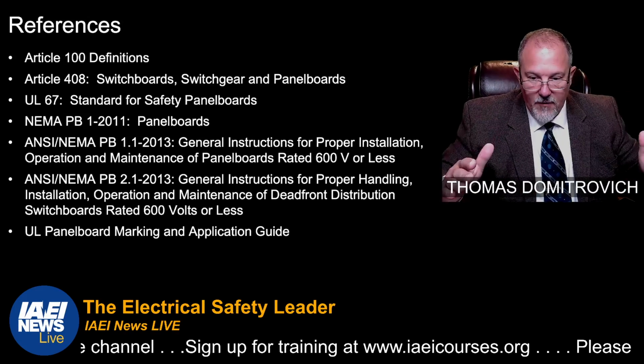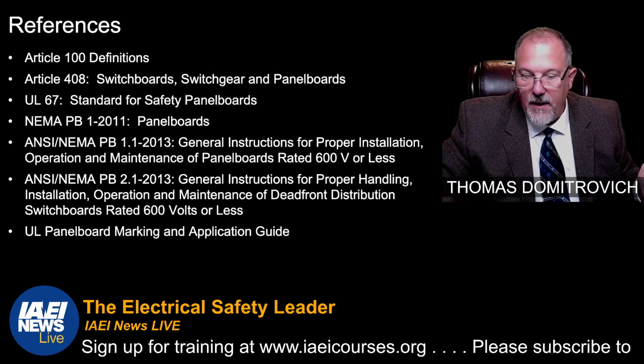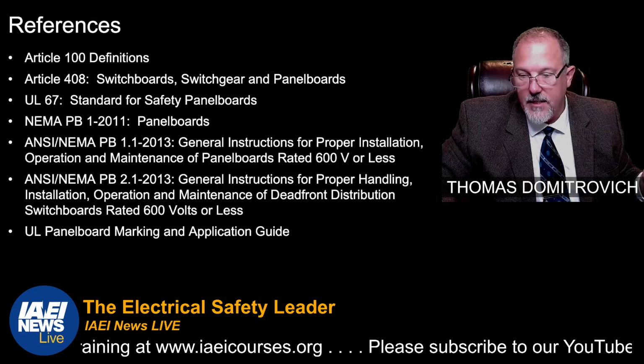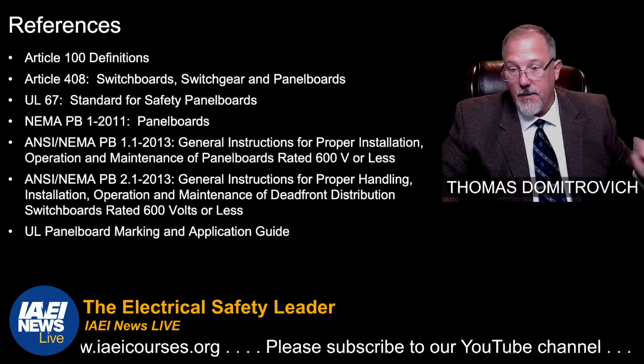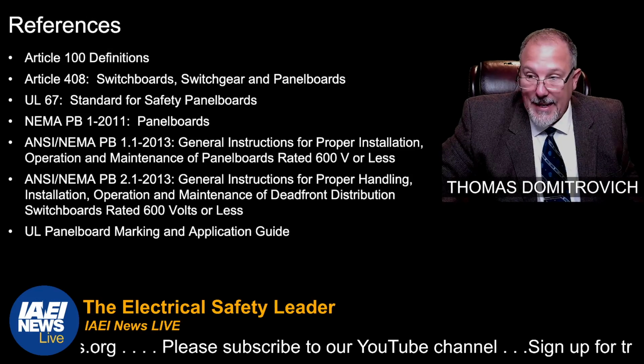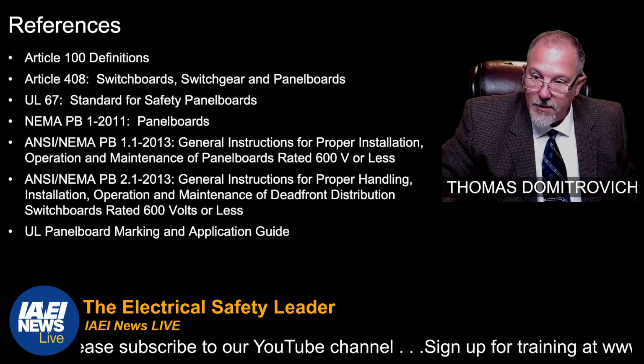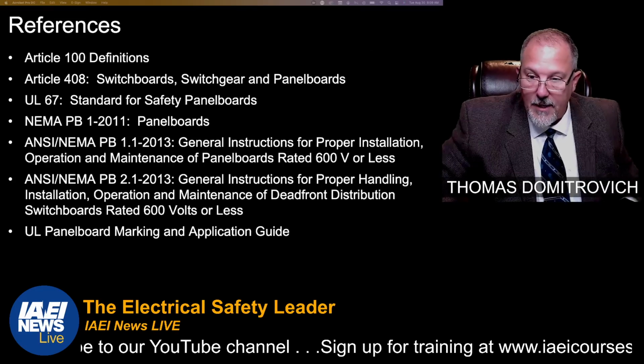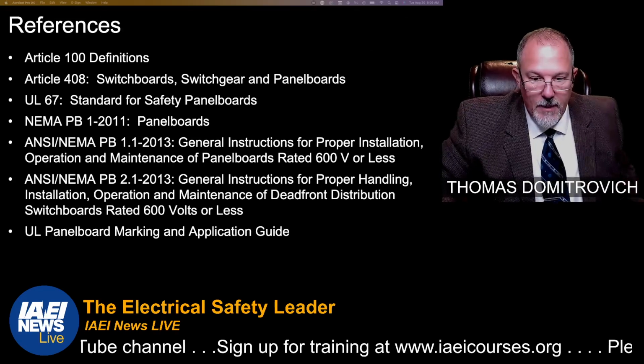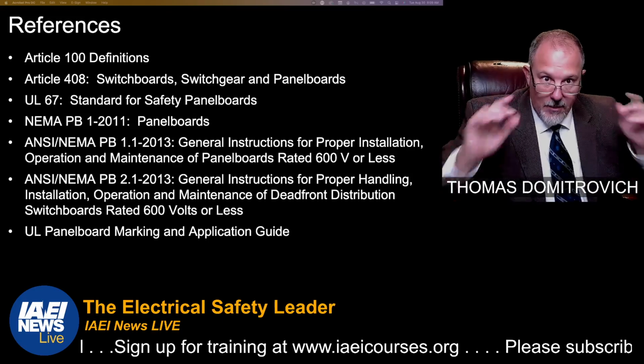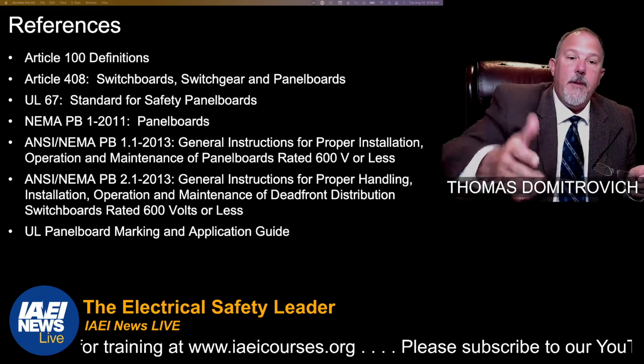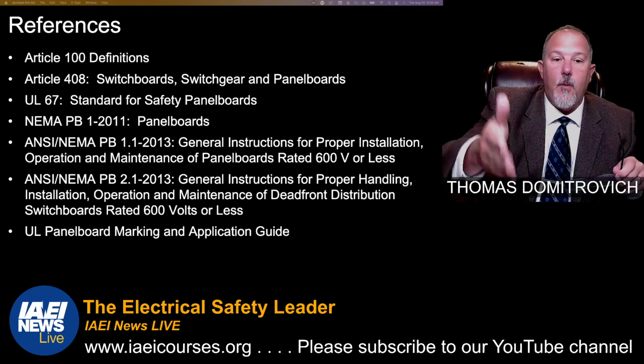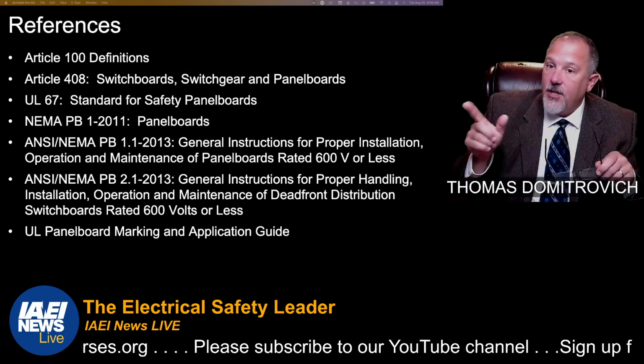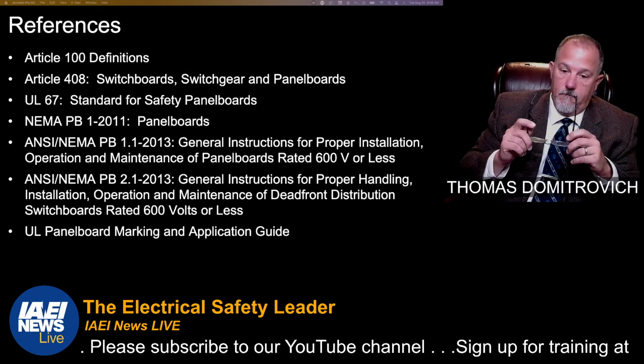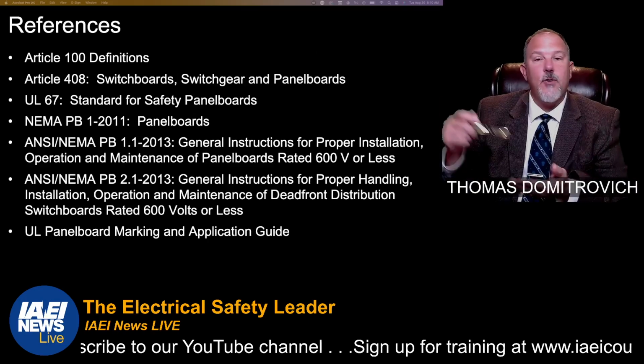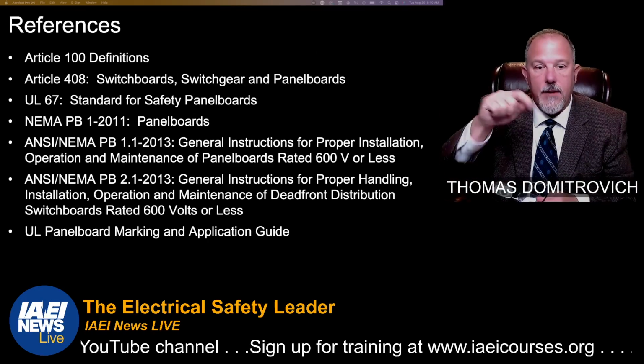So UL 67 for panel boards, April 18th, 2022 is the latest edition of the standard. So I'm going to download that one because I can, and I want to make sure that I have the latest version. Because if we talk about it, I want to be able to talk about it with you and reference it. Okay, so UL 67, NEMA PB1, NEMA PB 1.1 and 2.1, each of those documents are for free. All you gotta do is go up to the NEMA website. You can download those for free, and I've got the links down the bottom.